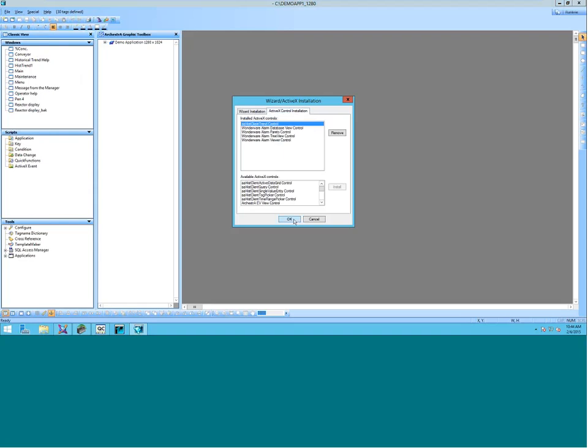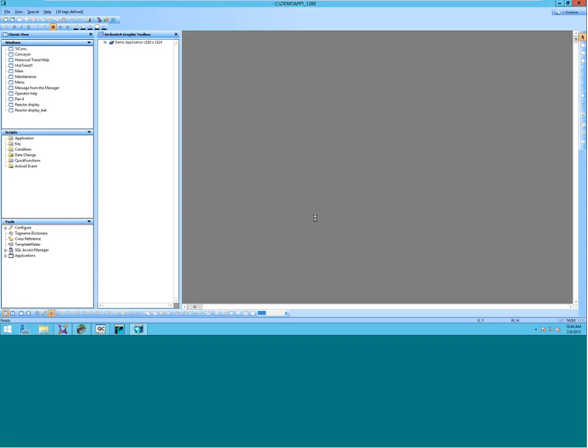Okay. Do I need to install GR on the InTouch node to use the modern version? Yeah, so that's a great question, and so that really is the benefit of the InTouch Modern, is that you don't have to do anything special right when you install. If you just want to use InTouch with ArchestrA Graphics, just pick when you do the product-based installation, just check the box for InTouch development. That's all you need to check. You don't need to check Galaxy Repository or IDE or any of that.